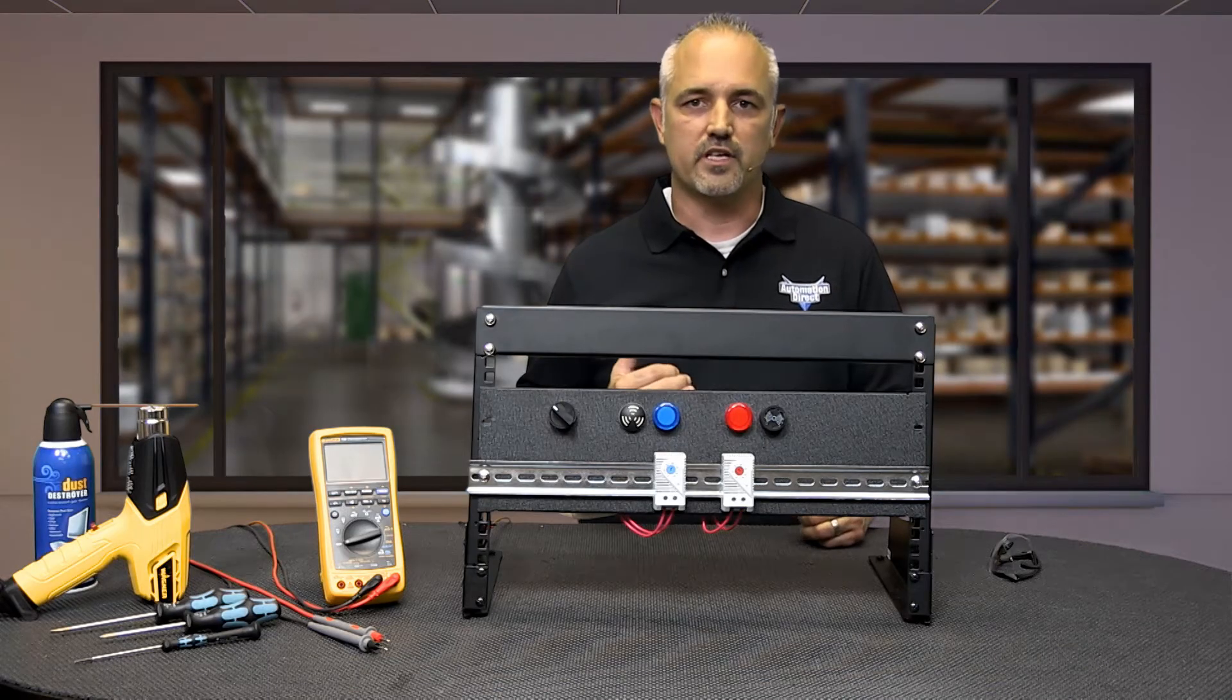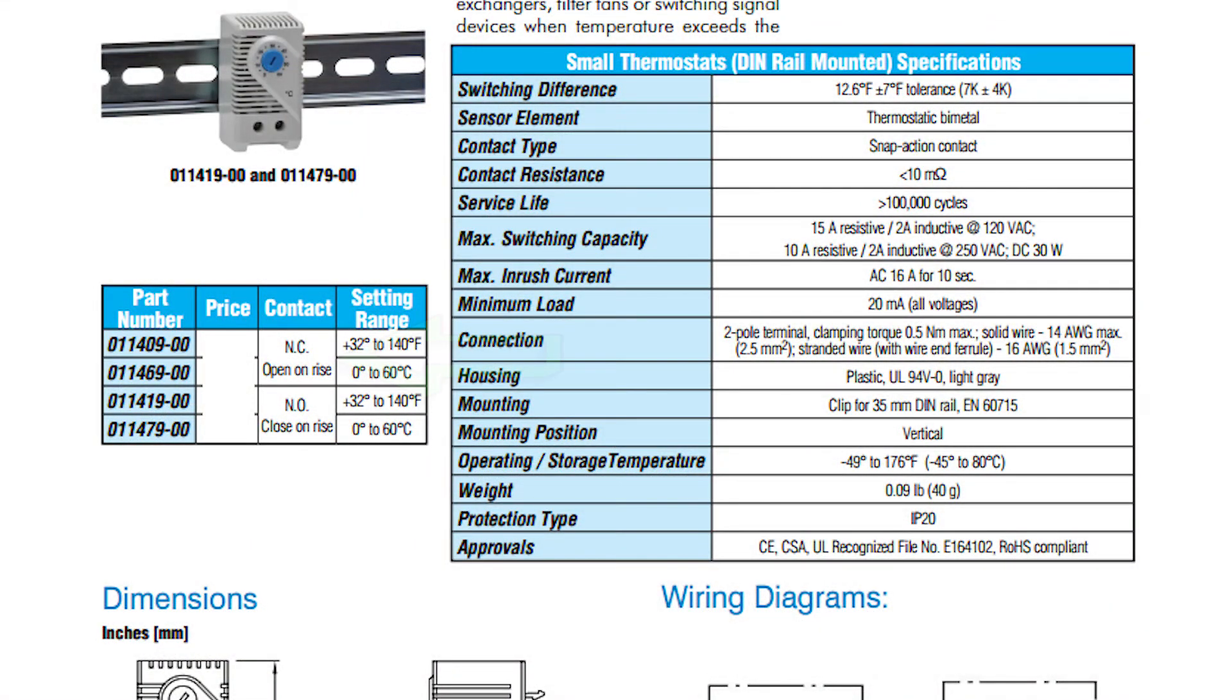Here is how these Stego thermostats operate. Normally closed is open on rise meaning the contact will open as the temperature rises and reaches the user setpoint. The contact will open turning off your device as demonstrated with the model 011409-00 with a red setpoint dial. These are used for regulating heaters or for switching signal devices.